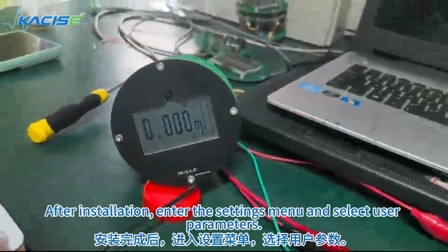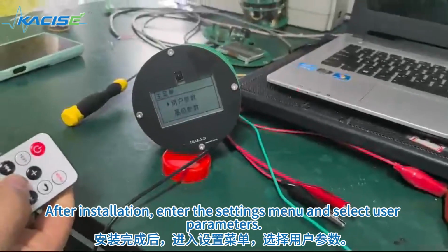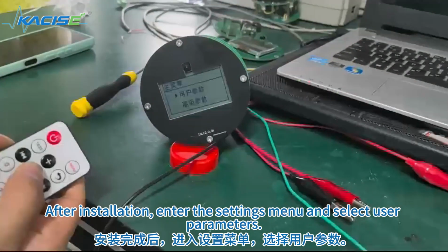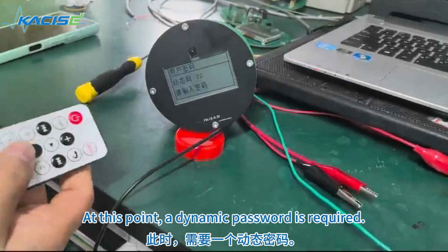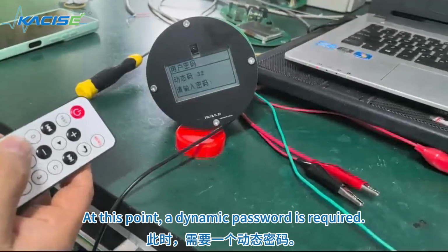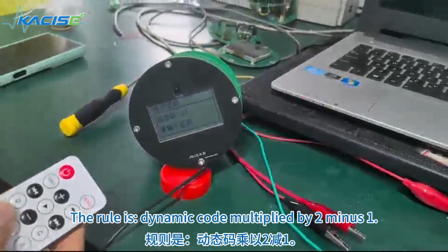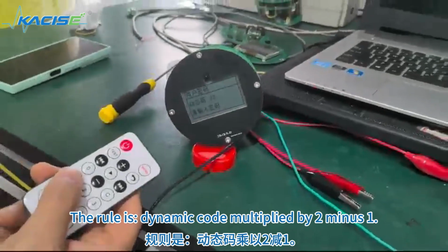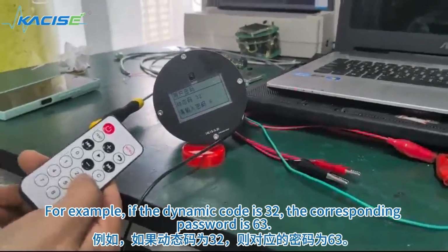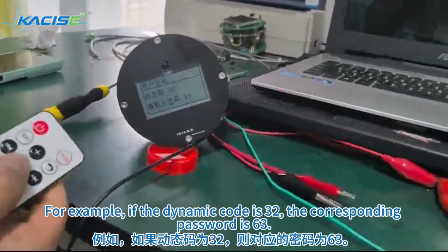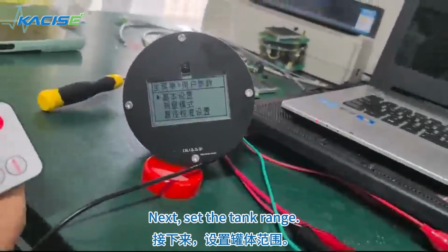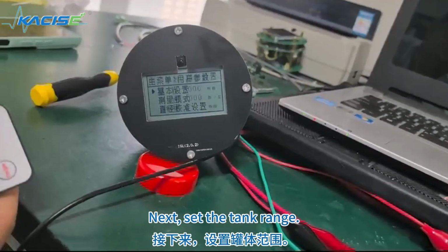After installation, enter the Settings menu and select User Parameters. At this point, a dynamic password is required. The rule is dynamic code multiplied by 2 minus 1. For example, if the dynamic code is 32, the corresponding password is 63. Enter. Next, set the tank range.